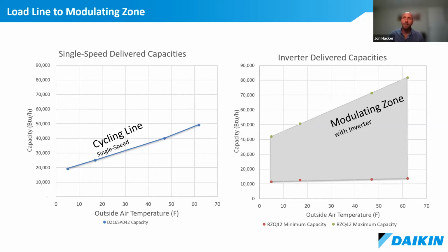Taking that same condition, 47 degrees Fahrenheit outside, the inverter product can deliver 40,000 BTUs, but it can also deliver up to 70,000 BTUs or down to maybe 12,000 BTUs. So we can now provide a wide range of capacities at that condition, which means we can modulate the capacity to precisely meet the needs of the home.